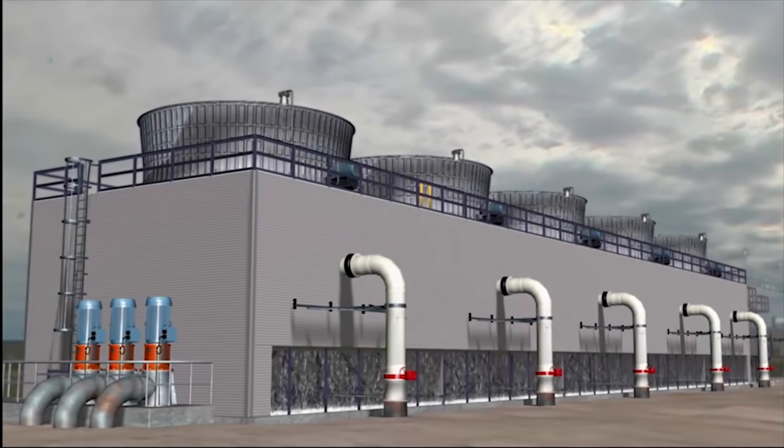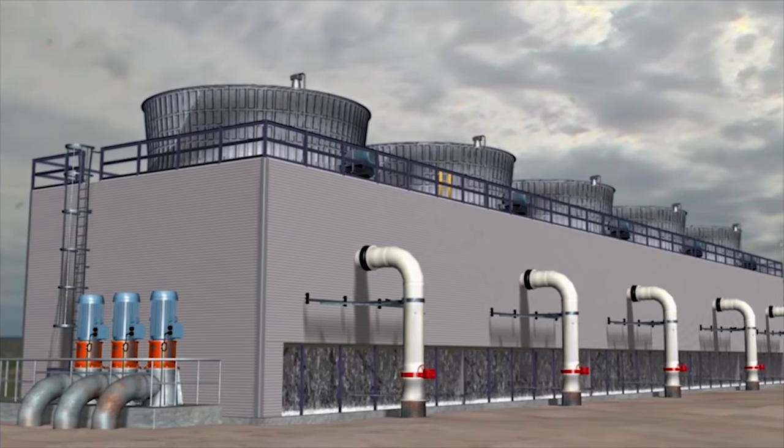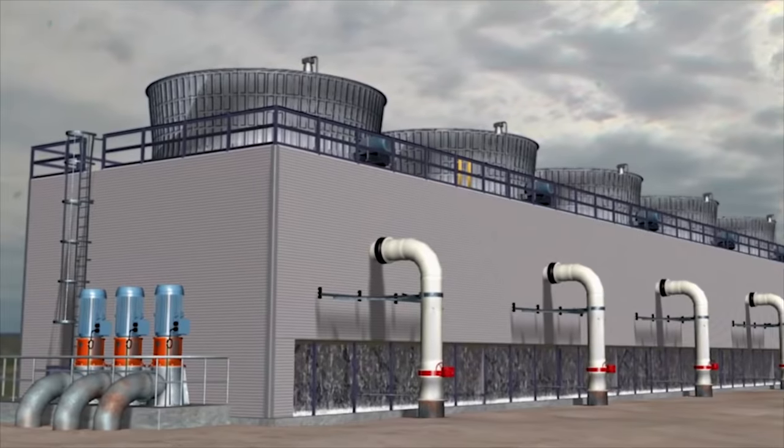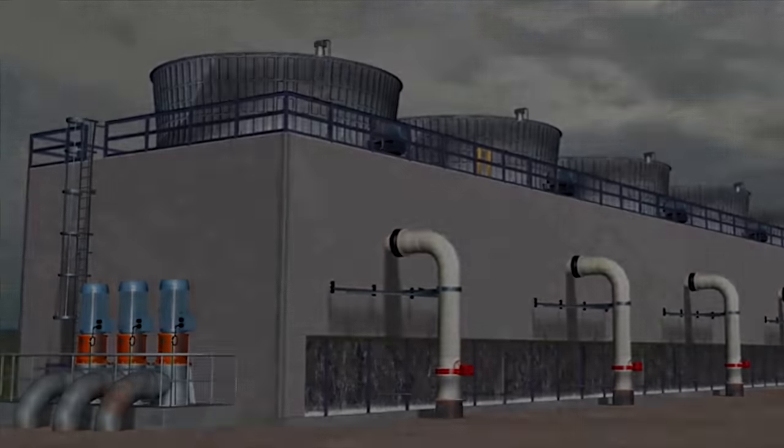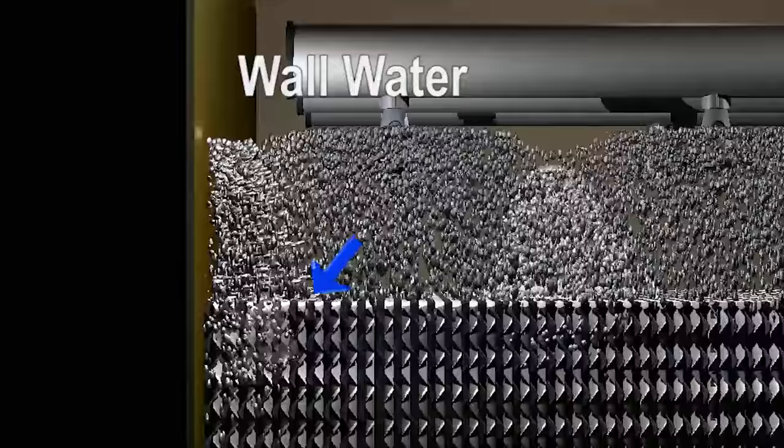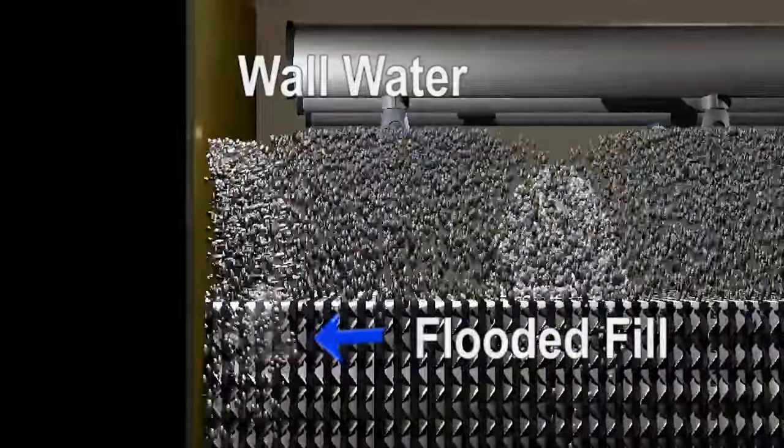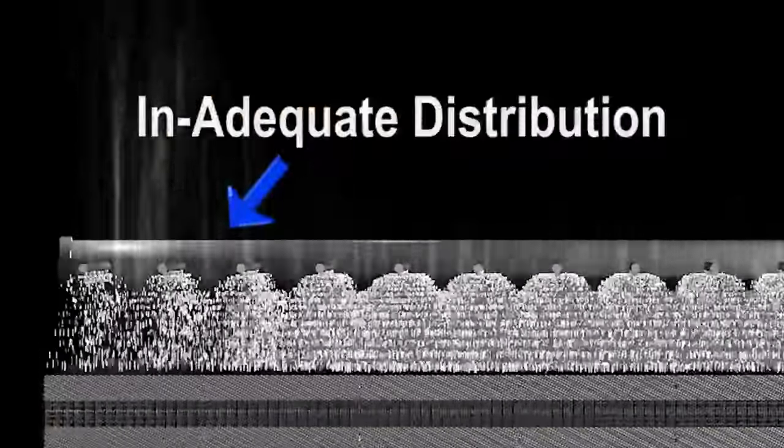Almost all of today's counterflow cooling towers have the same three problems that significantly downgrade their performance. Uneven water loading as a result of overlapping circular nozzles. Excessive wall water as a result of using circular nozzles and inadequate water distribution systems.